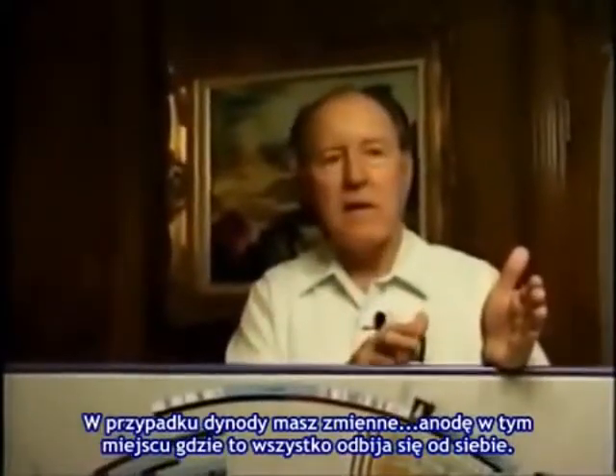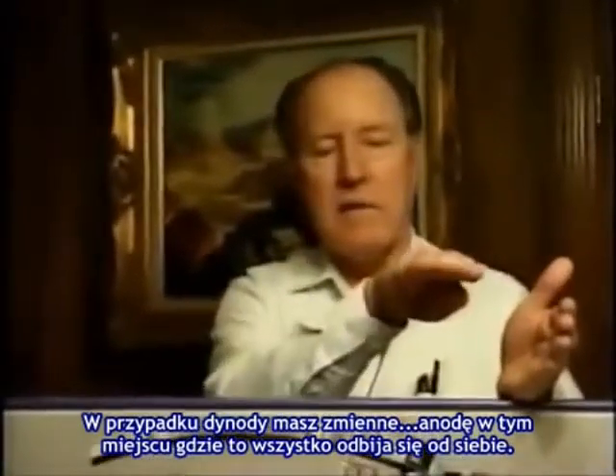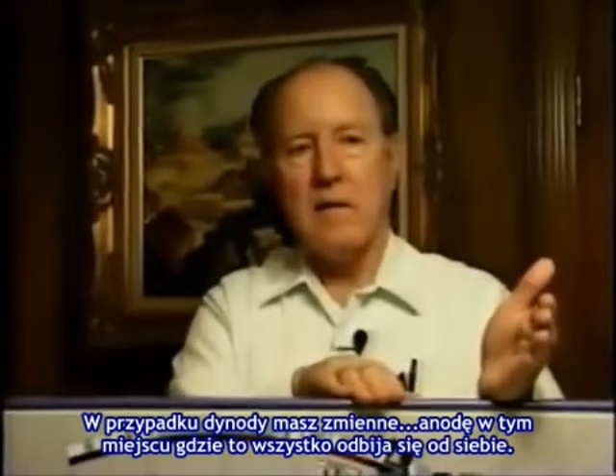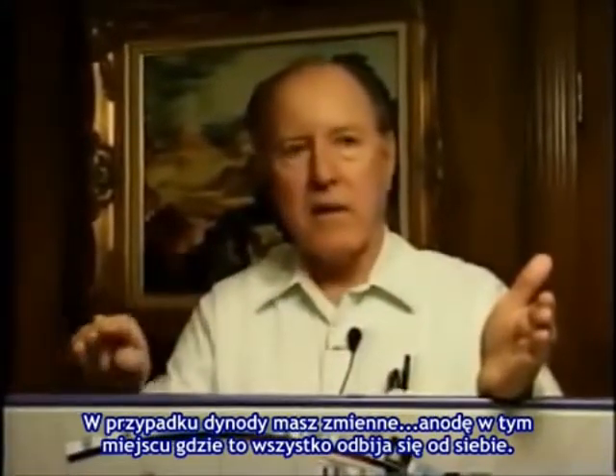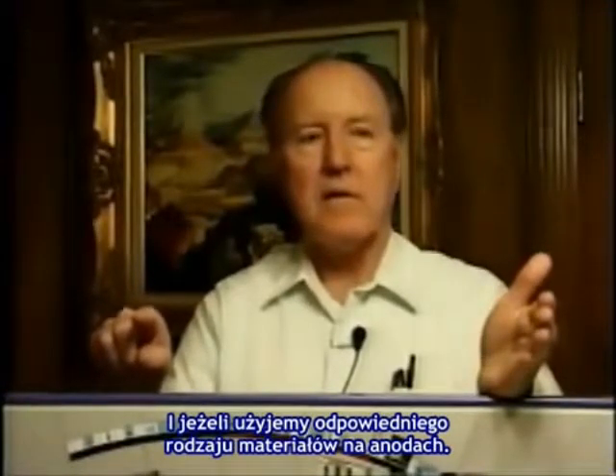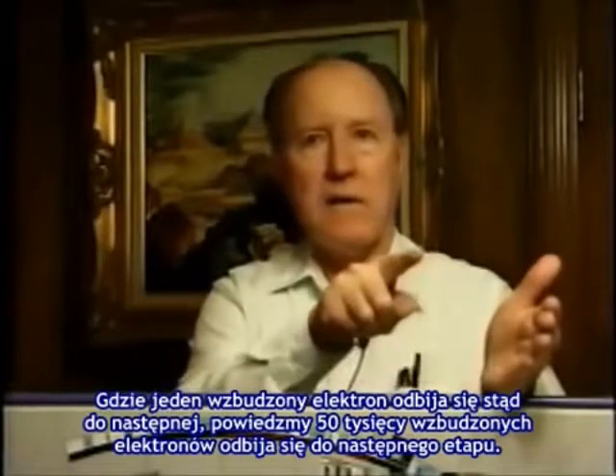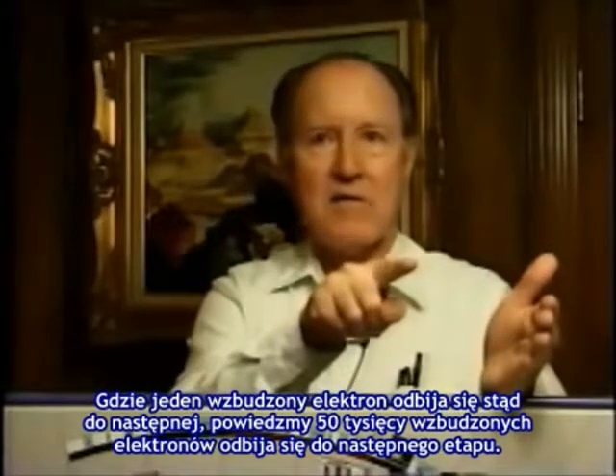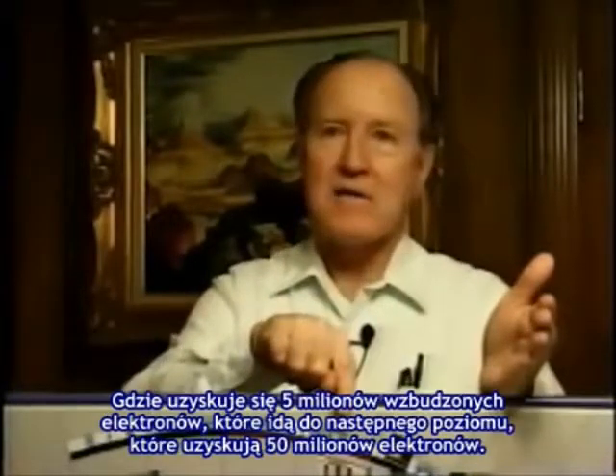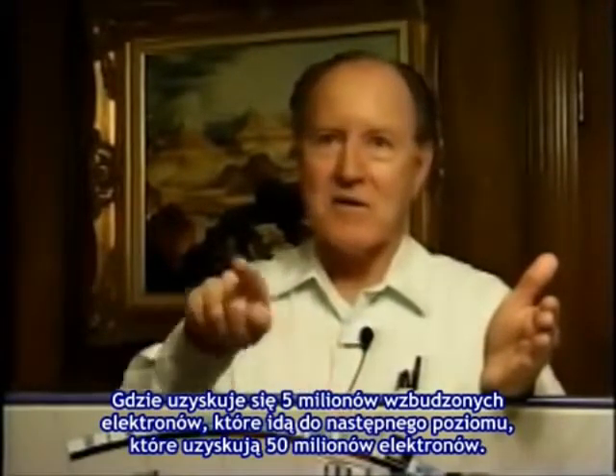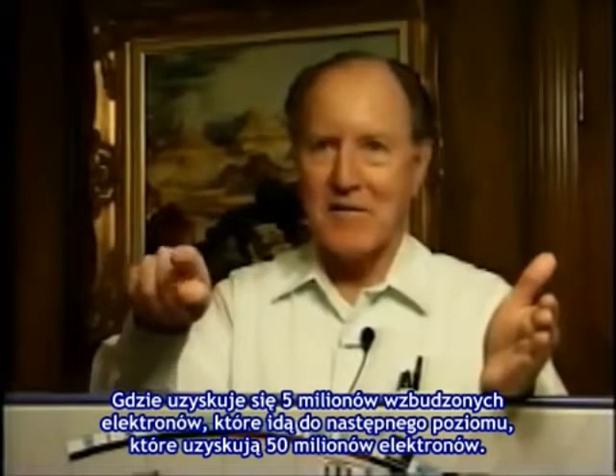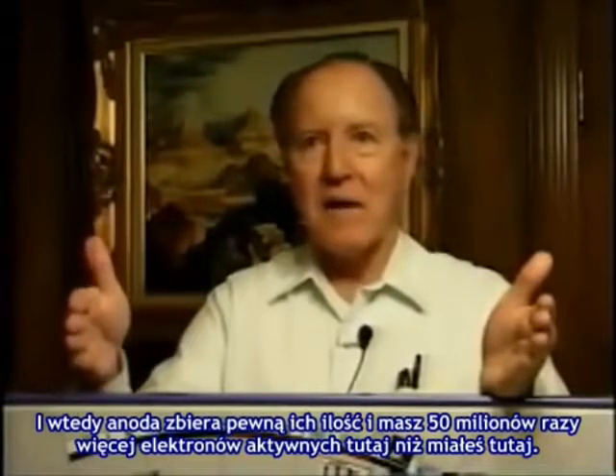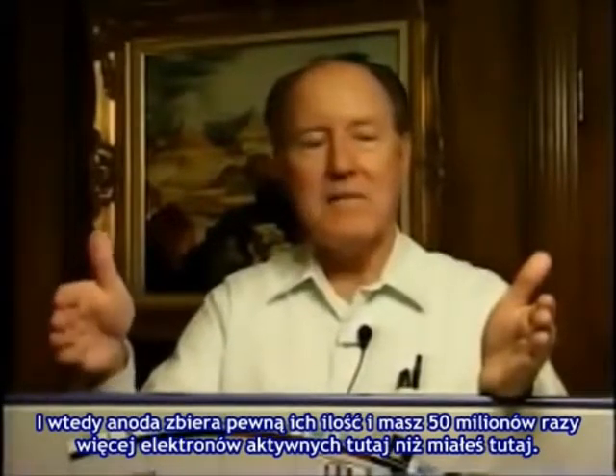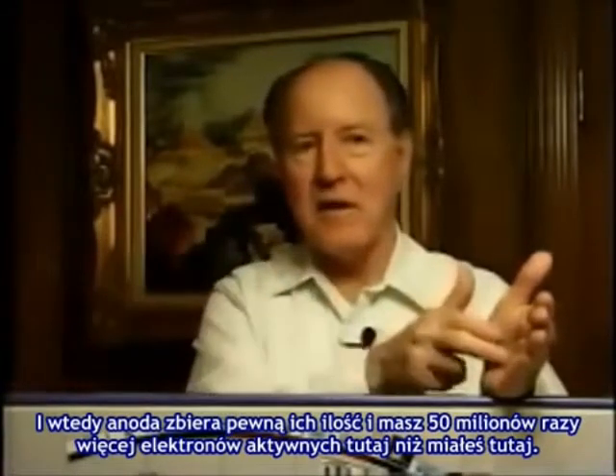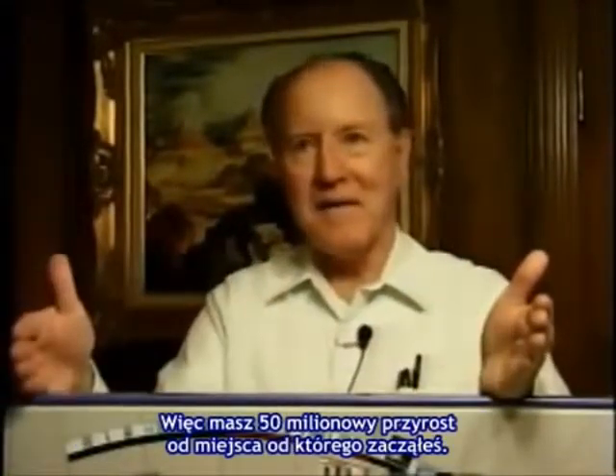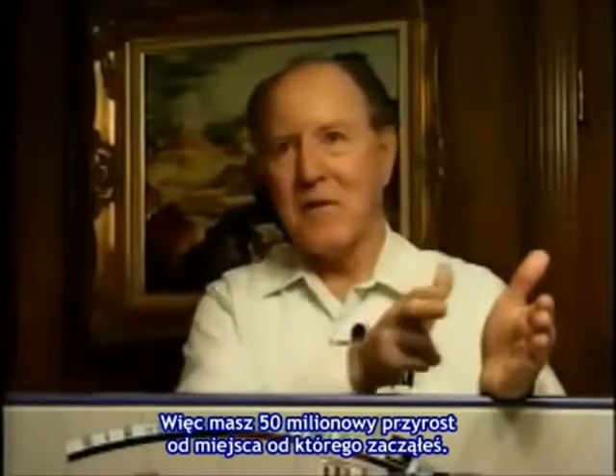In the case of the dynode, you have alternate anodes in here which this thing is bouncing off of. If you have a certain type of material on these anodes, one electron leaving here and bouncing to this one knocks, say, 50,000 electrons loose, which bounce to the next stage, which knocks 5 million electrons loose, which goes to the next stage, which knocks 50 million electrons loose, and then the anode here collects them. So you have 50 million times the amount of electrons active here that you had originally, so you have gained 50 million times what you started out with.